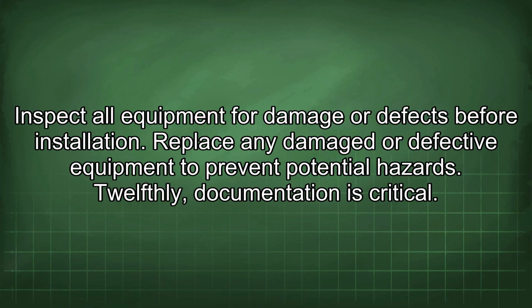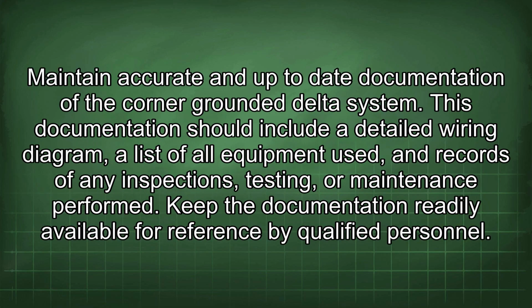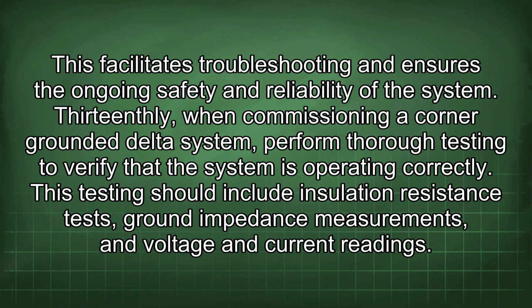12thly, documentation is critical. Maintain accurate and up-to-date documentation of the corner-grounded delta system. This documentation should include a detailed wiring diagram, a list of all equipment used, and records of any inspections, testing, or maintenance performed. Keep the documentation readily available for reference by qualified personnel. This facilitates troubleshooting and ensures the ongoing safety and reliability of the system.